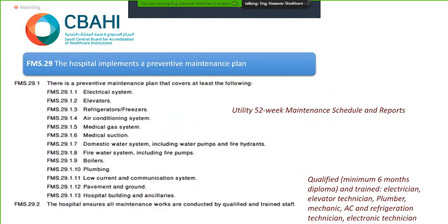Preventive maintenance should cover the following: we should have a utility 52-week maintenance schedule and reports. I have seen several hospitals prepare one A0-size sheet listing electrical, mechanical, and plumbing systems for weekly, monthly, or annual maintenance. Qualified or trained technicians should be available, and the hospital should prove they have a minimum 6-month diploma.